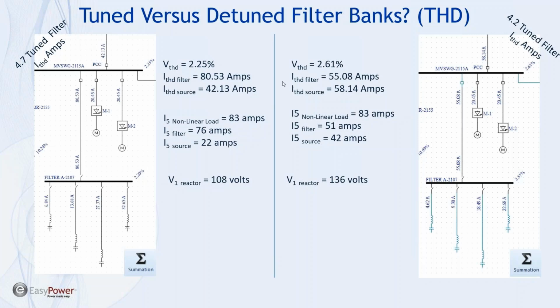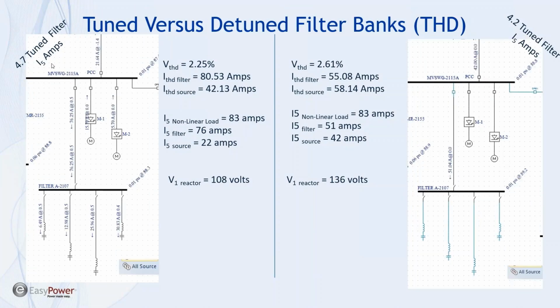So here we're looking at just I5. We're doing an all source current injection here. So we're looking at what's going on at the fifth. And remember, this is 4.2 tune. We can see that for 4.2 tune, we have 51 amps of harmonic current, at an angle of 0 degrees. Here, we have 76 amps at an angle of just 0.5 degrees.